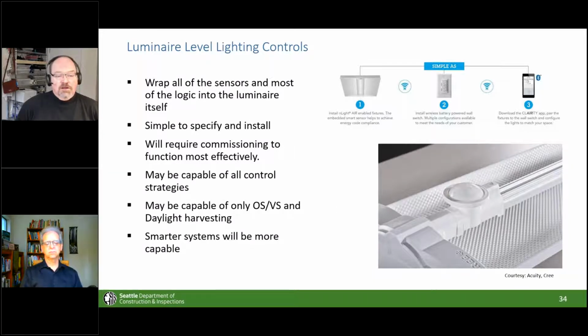We also have sensing technology, so most of the time that means occupancy sensing, vacancy sensing, and daylight sensing. Sometimes that means other things, like CO2 monitors or temperature monitors, a variety of different things. But the idea is that everything gets wrapped together right out of the factory. So instead of pairing devices or running additional wires, you basically put your light fixtures up into the ceiling, have 3 connections—a hot, a neutral, and a ground—and you're done. Then everything else becomes programming.